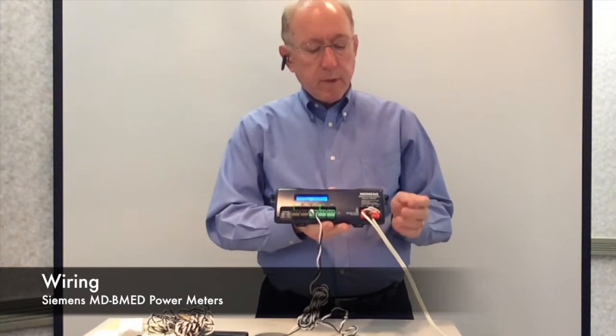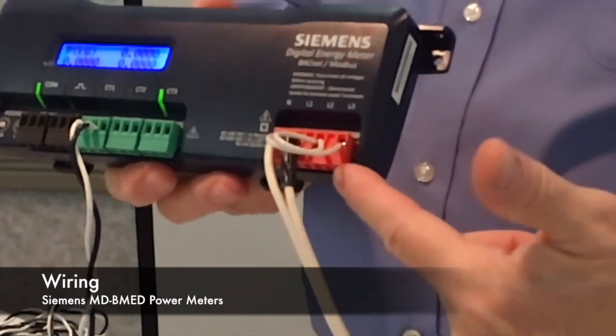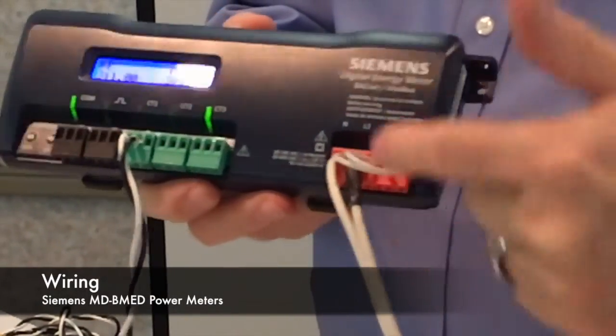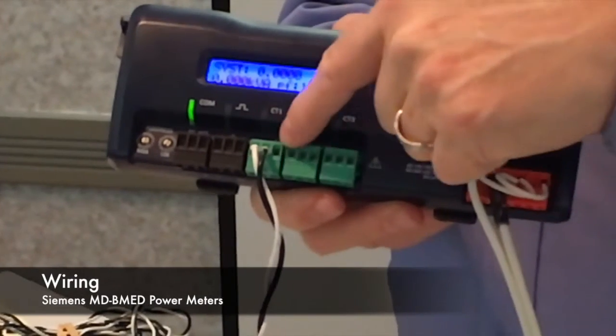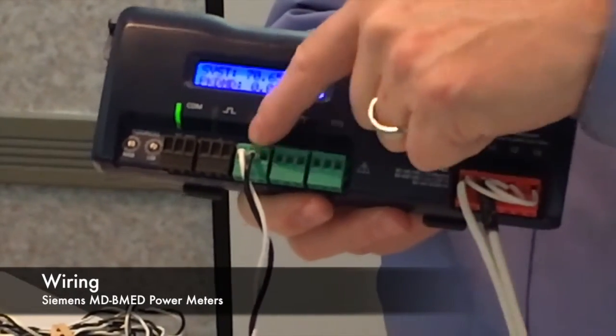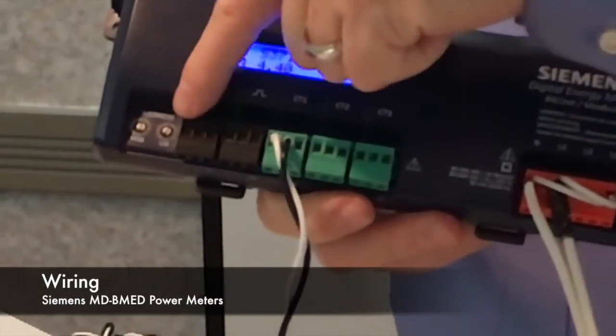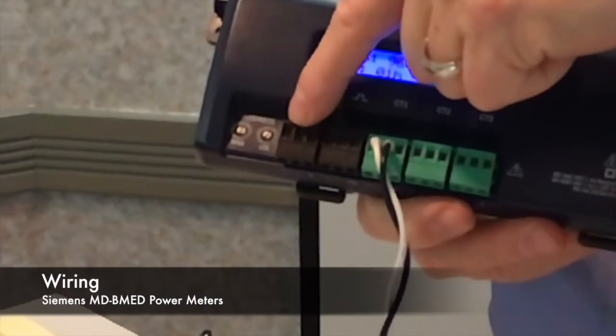The MD series meter is extremely logical and easy to wire and to use. In the first case, the single phase or three-phase wire goes into the red connectors. Your three CTs are wired individually into separate pluggable connectors, these green connectors. Your RS-485 communication goes in the black connector. The other black connector is for a digital output that can be programmed to mimic a digital output pulse that you would get off of a normal energy meter.